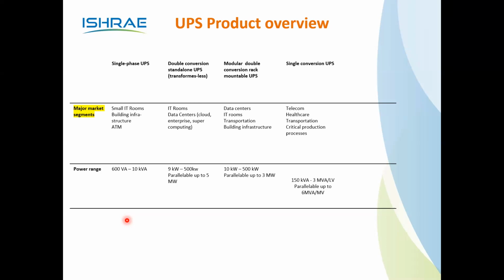Another one is the modular UPS. Here the rating starts from 10 kilowatt and above. There are some technologies, certainly, with 5 kilowatt also available. Here the solution is available up to 3 megawatt. Modular UPS is meant for critical applications as well as scalability. As and when required, we can upgrade the UPS capacity instead of going for the higher capacity from day one. That is the main concept for going for a modular UPS.